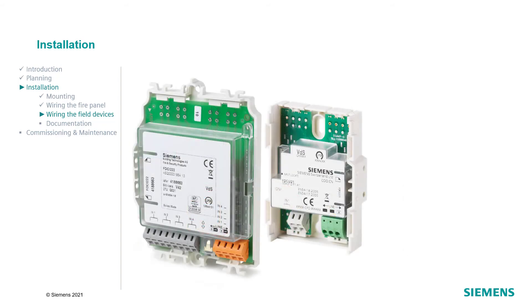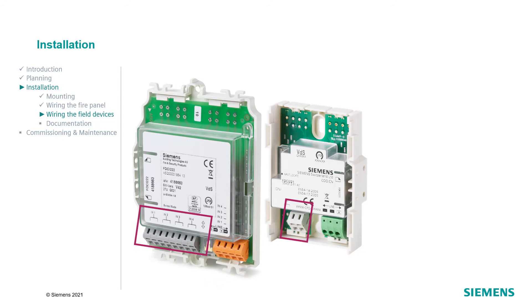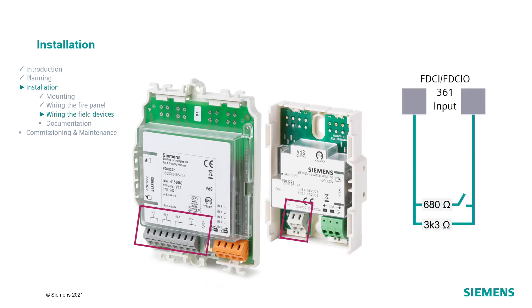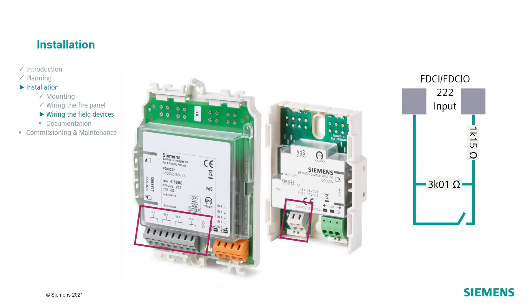And now we will go on with the connections of the I.O. modules. The inputs of the I.O. modules are monitored for open line and short circuit. In order to facilitate this, two resistors must be connected to the end of the input lines as shown in the following diagrams. The FDCI361 needs a 680 ohm resistor and a 3K3 ohm resistor. The FDCI222 needs a 1K15 ohm resistor and a 3K01 ohm resistor.